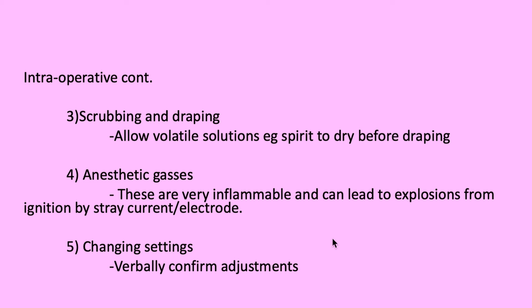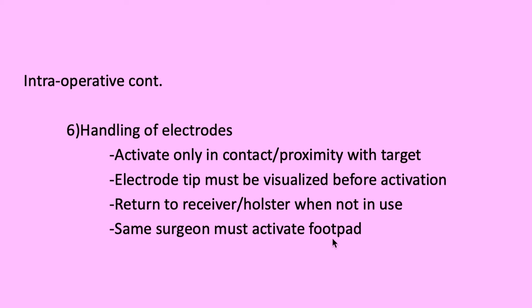The diathermy pencil should be kept in a quiver — a non-conductive holster — when not in use, rather than on the patient or just lying around. The handpiece should always be placed in a non-conductive holster when not in use. The most common non-conductive holster in theaters is the quiver — a hollow cylindrical container used to keep the diathermy pen. We should always use the lowest possible generator setting that will achieve the desired surgical effect.